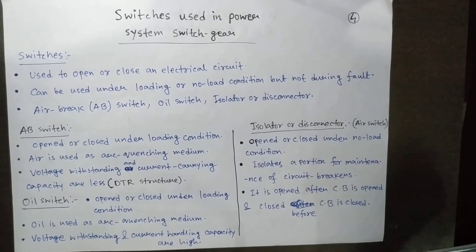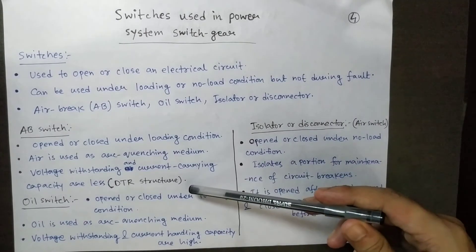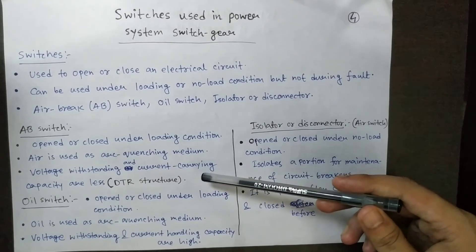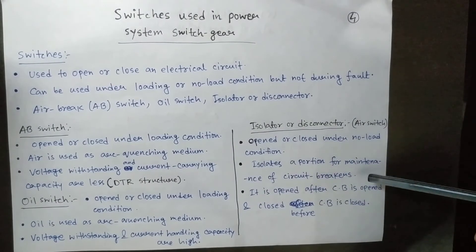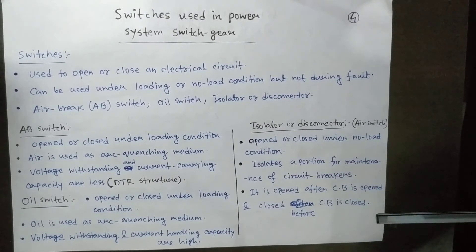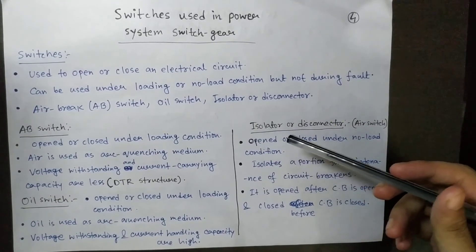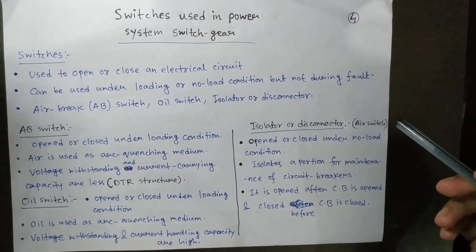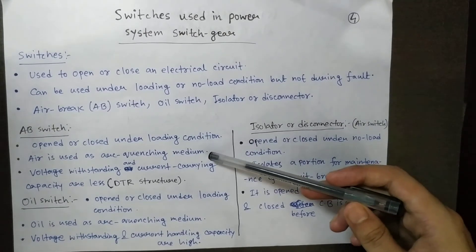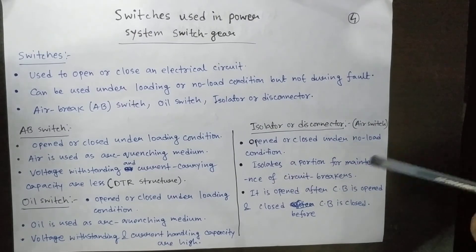The AB switch is mainly used in DTR structures whenever maintenance, replacement, checking, or repairing of transformers is needed. The isolator is mainly used with circuit breakers — when performing maintenance of circuit breakers, isolators are used. Both serve the same fundamental purpose of providing isolation, but one operates under loading conditions and the other only under no-load conditions.